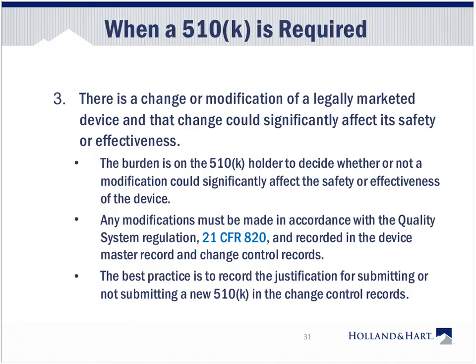Any modifications must be made in accordance with the quality system regulation and recorded in the device master record and change control records. My strong recommendation, the best practice, is to record the justification for submitting or not submitting a new 510K in the change control records. So if you are looking at taking an existing device and marketing it for some other purpose, there has to be some analysis on your part as to whether or not it requires a new 510K. And no matter what you decide, I would strongly recommend that you document that decision process and your reasoning, because it can come back to protect you in a very big way.